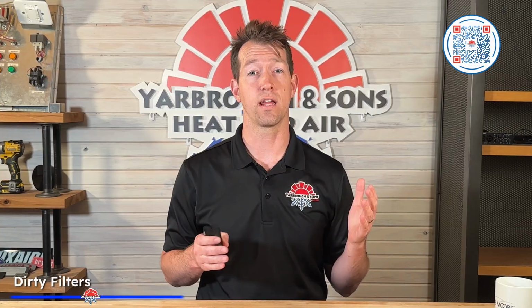The evaporator coil, which is the cold coil inside your air handler, can't pick up enough heat from the air. So it starts getting colder and colder and colder until it freezes solid. At that point, you've got a block of ice on your indoor unit, zero airflow, and a house that won't cool. So here's the fix. Turn the system to fan only. Let it thaw for 2 to 4 hours, replace the filter, and then restart.